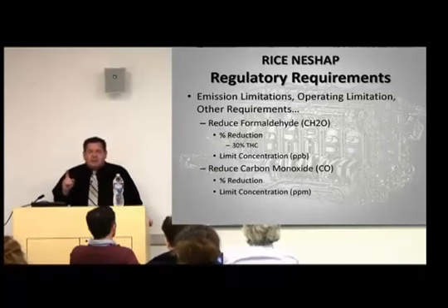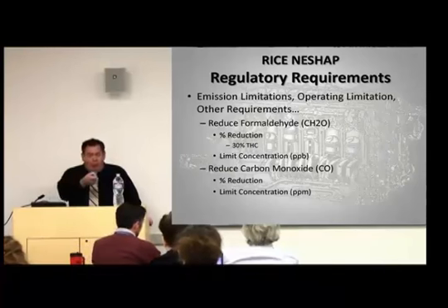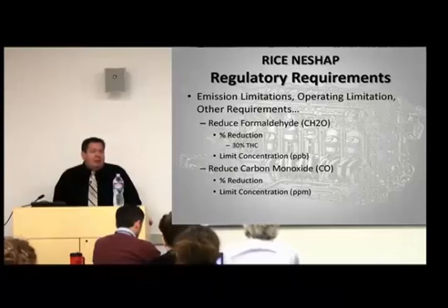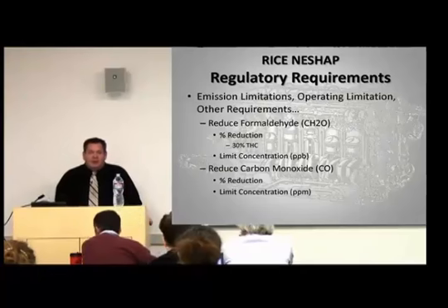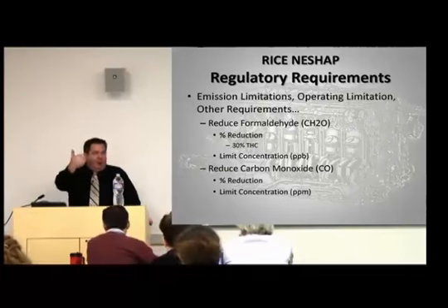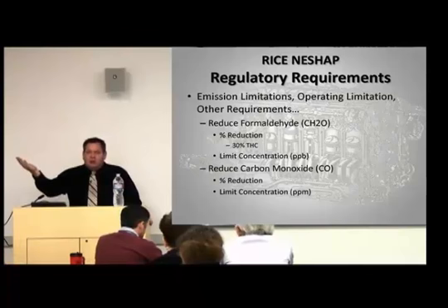One exception up until recently has been 4-stroke rich burn engines. In your cheat sheet, it says 4-stroke rich burn engines have to comply with a formaldehyde limit. Well, this is problematic to the industry, because when the industry orders a source test for an internal combustion engine, source testers automatically think carbon monoxide, volatile organic compounds, hydrocarbons, oxides of nitrogen, qualifying gases of CO2 and oxygen.